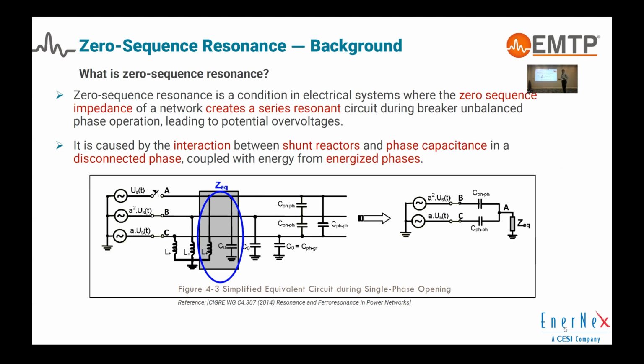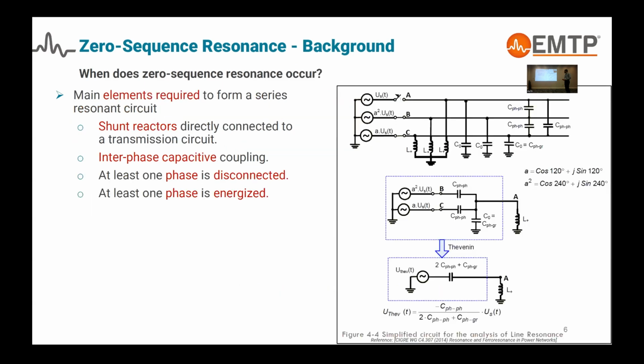So this zero sequence resonance would happen. It would be an interaction between the shunt reactor, phase capacitances, the disconnected phase, and energy from the connected phases. I will move to the next slide. The main elements required for this zero sequence resonance are the shunt reactor and interphase capacitances, and it also needs at least one phase to be disconnected, and at least one phase to be energized.